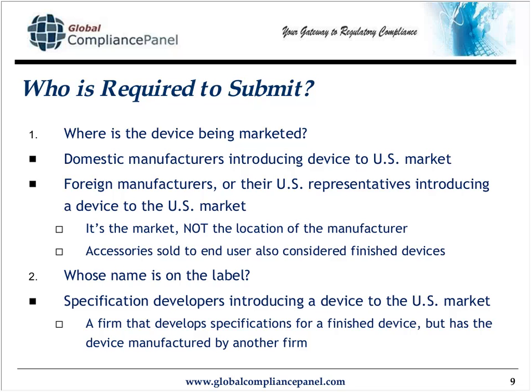Second question to ask yourself in determining who is required to submit a 510K is whose name is on the label. With regard to a specification developer who is introducing a device to the U.S. market, consider a firm that develops specifications for a finished device but has the device manufactured by another firm. This firm does need to submit a 510K.